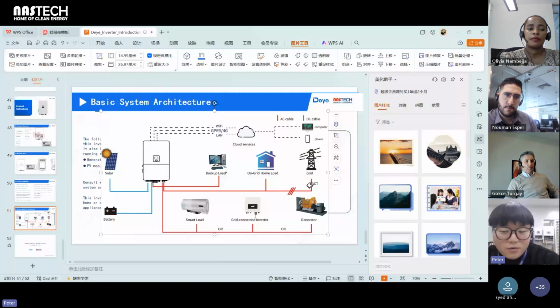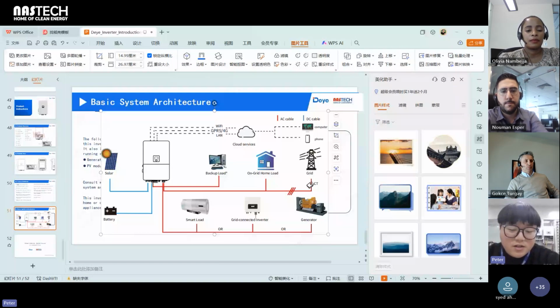So in 1 hour you can provide 400 kilowatt hour, and in the daytime maybe multiply by 6 or 7, you will get your general daily production, but not accurate. You can have a reference, like 2,800 kilowatt hour in 1 day you can produce, and minus your daily consumption in the daytime only, and the left energy is the energy that you want to store in your battery. And when the night comes, you can discharge this power from the battery. So you can calculate that number, then you can know how many batteries you need to store the leftover daily production power.